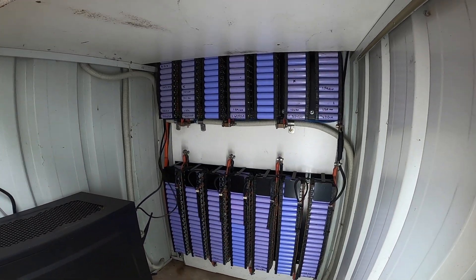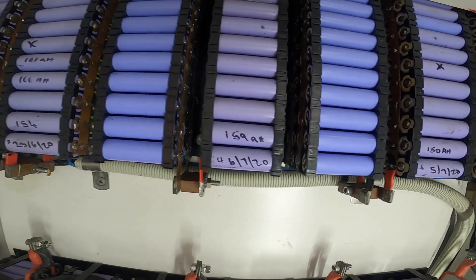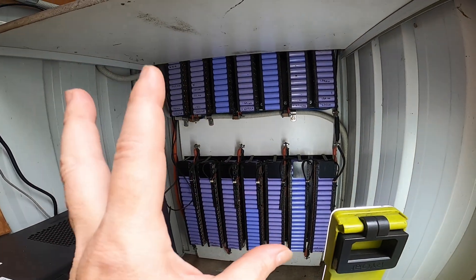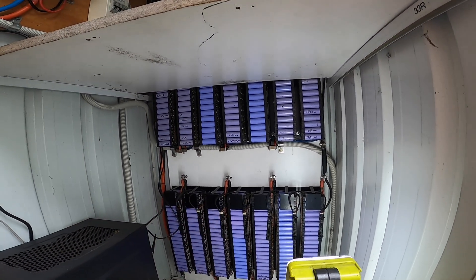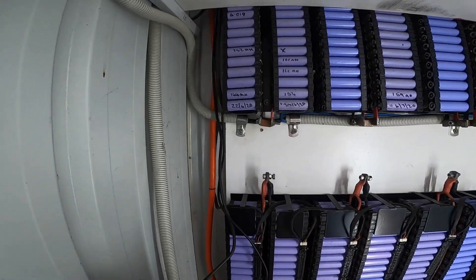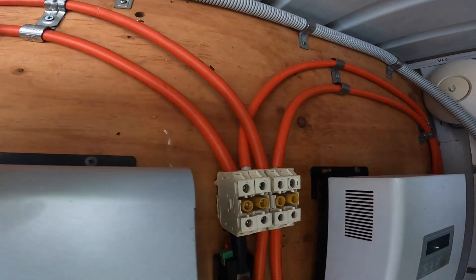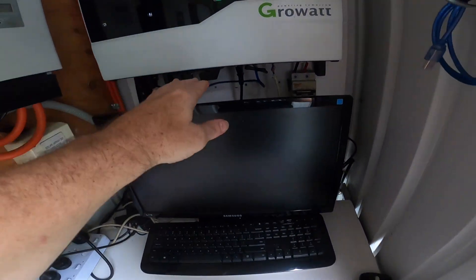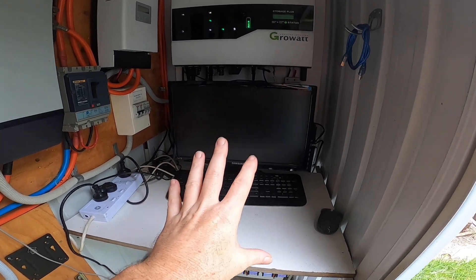It's probably about 30 days since I've been down here. If you have a look at some of these cells, we've got 2020 on that — so they're three years old, or at least that's the last time they were checked. There are a lot of 2020s down there, and these ones seem to be failing more than the shed behind me. The only thing I can put that down to is these cells have cables that are about two to three meters longer than those ones, so they get the voltage sag more. I'm figuring the load on those batteries causes these ones to fail quicker.